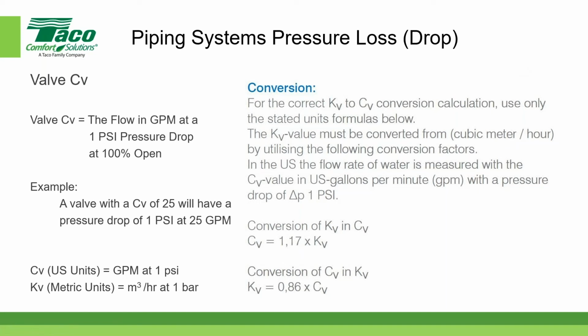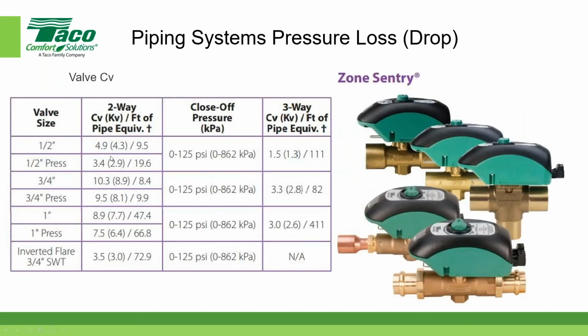Yeah, so if you wanted to find the KV for a valve and you were given the CV, you'd multiply by 0.86. So if you'll notice over here, 4.9 times 0.86 is approximately 4.3, rounded off.